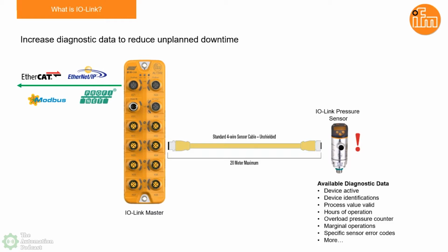Now that we're able to open this up - a lot of sensors in the market are pretty smart, driven by microprocessors with firmware running on them, and there's tons of data you can access. The problem is, a few years ago you didn't really have a chance to access that data because the controls architecture of the world didn't allow for it, or there wasn't a way out of the sensor to do that. But now with IO-Link, we have the ability to access all the different parameters and information from that microprocessor and bring it to the controls world.